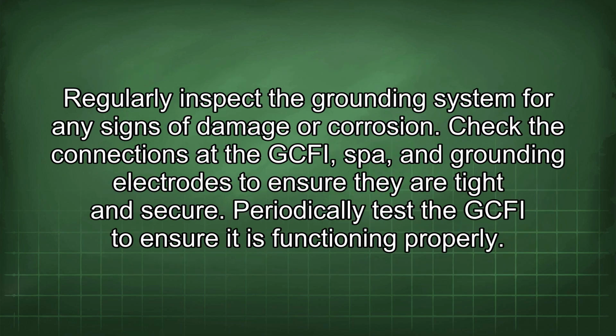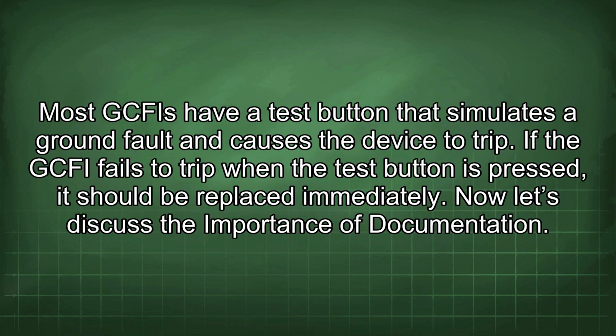Regularly inspect the grounding system for any signs of damage or corrosion. Check the connections at the GFCI, spa, and grounding electrodes to ensure they are tight and secure. Periodically test the GFCI to ensure it is functioning properly. Most GFCIs have a test button that simulates a ground fault and causes the device to trip. If the GFCI fails to trip when the test button is pressed, it should be replaced immediately.